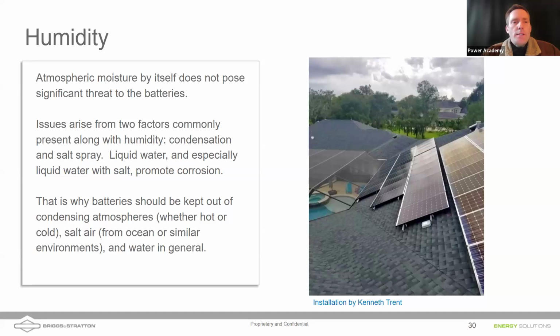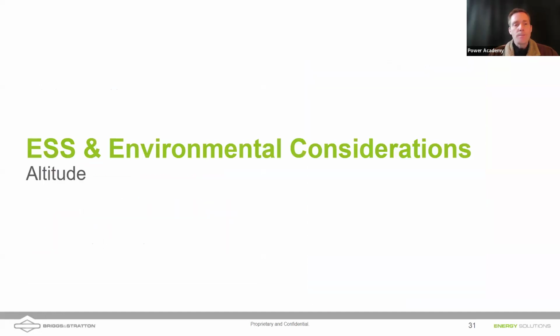It's also important to consider atmospheric conditions. Outdoor rated batteries like our SimpliPhi 4.9 and the SimpliPhi 6.6 are protected from environmental risks, but moisture can cause problems even to batteries stored underneath a roof, due to high humidity levels. Keeping batteries inside a cabinet can reduce the amount of humidity they are exposed to as well. For others using batteries, I would not recommend the use of our batteries on yachts and boats, especially if they're going to be in a location where they could get salt spray. You would really want to have a sealed battery for that.